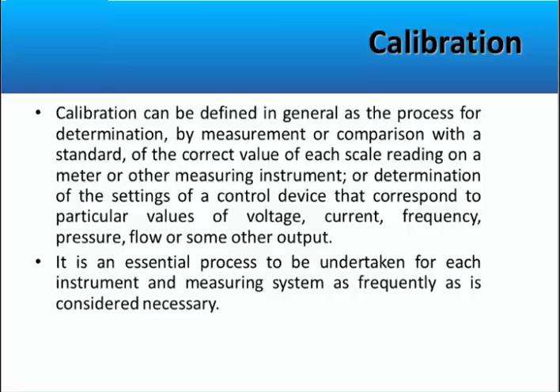Calibration is an important aspect in most professional industries, in that it is used to verify that the system is actually recording a process that needs to be monitored. There are several specific steps in calibration. The first is to make sure that the instrument you're using to measure a parameter is within specification, and firstly that has to be tested against a known reference. It then has to be altered if it is outside that particular point, and then re-verified to make sure that it is within calibration once again.